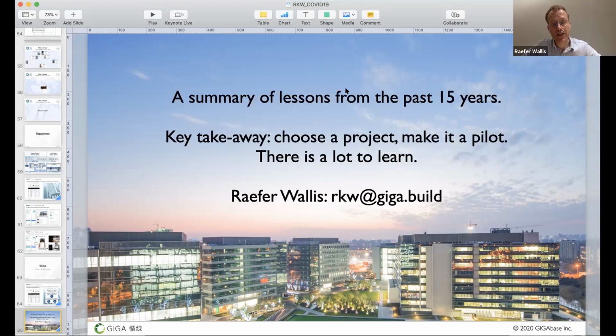So my recommendation is really to start with the data. We've worked on a ton of existing buildings where people design what they think is a solution, put it in, and then look for results—and typically have to spend quite a bit of money to readjust. I'd really recommend putting in the sensors first, capturing the data outdoor, pre-filtration, post-filtration, indoor, and then adjusting the system based on that. You might find that allows for some tinkering as well.